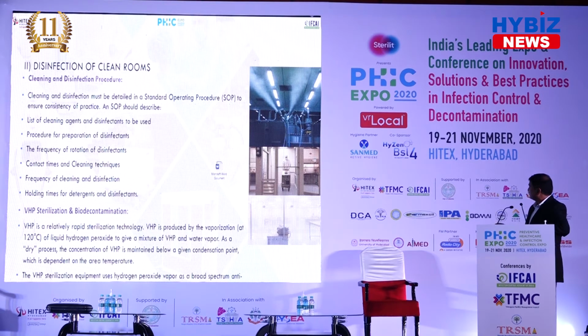This is the portable aerosol, that is, a hydrogen peroxide vapor generator. Nowadays many vendors are injecting the hydrogen peroxide into the AHU system itself, that is, into the ducts of the air handling units, so that the vaporized hydrogen peroxide for decontamination enters through the ducts of the AHU and through the filters, and circulates through the entire clean room.